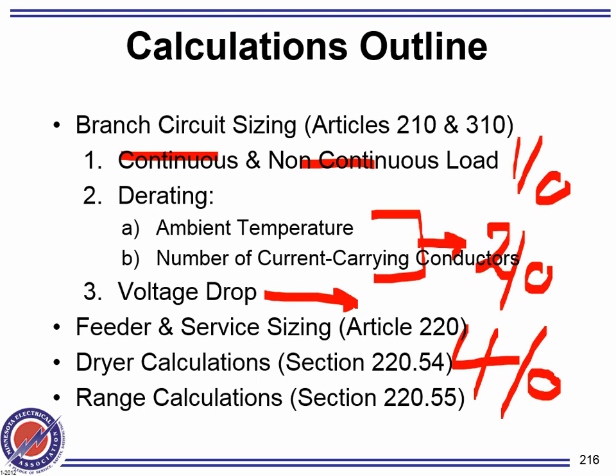Three separate unique calculations. On the test, guys, they don't give you the three at the same time. They give you two though. They give you derating and bundling and continuous load. So what do you do? Calculate based on continuous load, put it aside. Calculate based on derating and temperature, put it aside. Choose the largest of the two, and you're done.